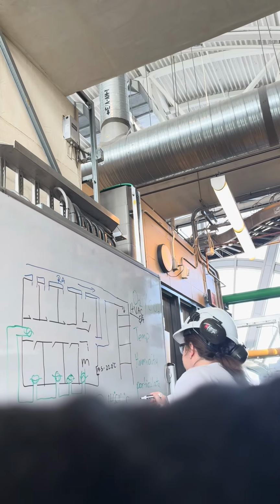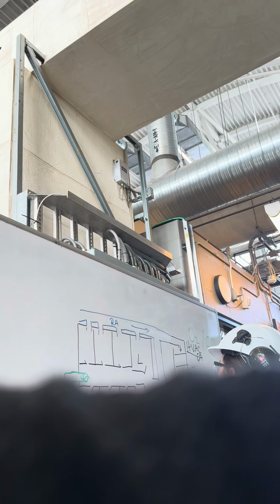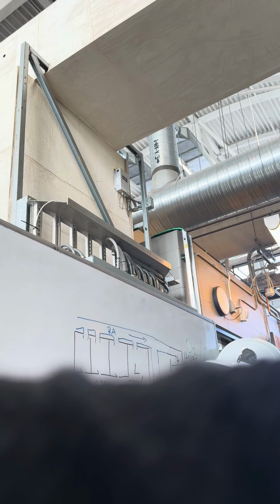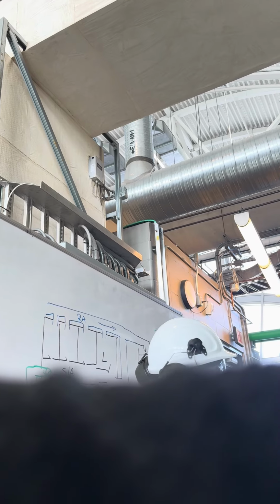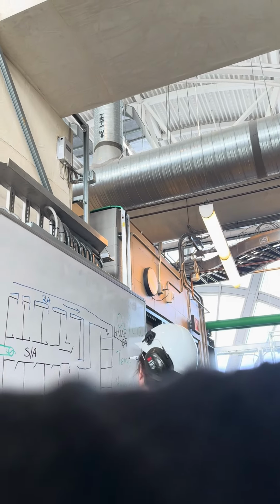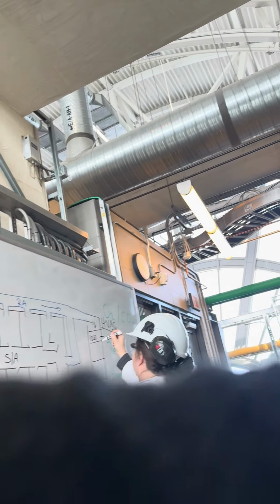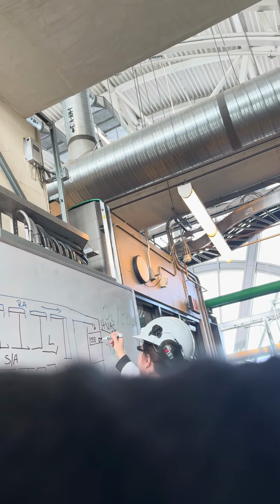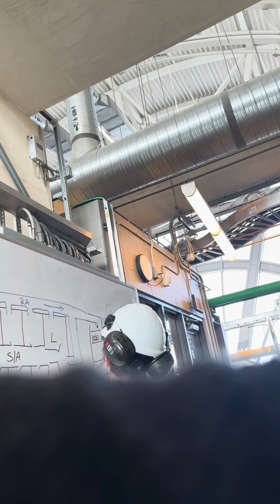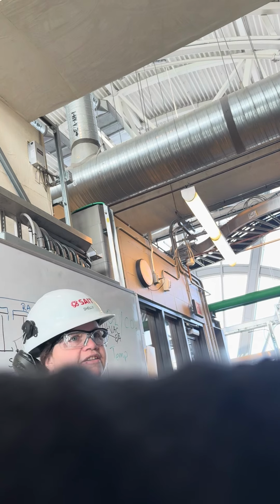So outside air coming in, supply air to the rooms, return air going back to your HVAC, and if we have 100% exhaust air, we're constantly bringing in 100% outside air. It's costing us a lot of money, because we're paying to heat it, humidify it, and clean it - the filters have to be replaced. But very rarely will you work with a place unless it's like a hospital or research center where you have to have 100% filtered outside air, and then they add those extra filters to clean it with.